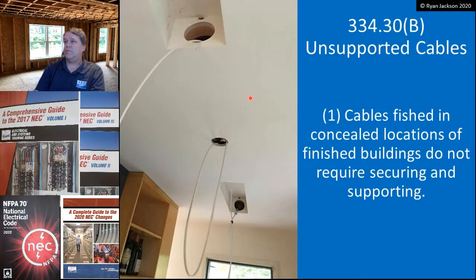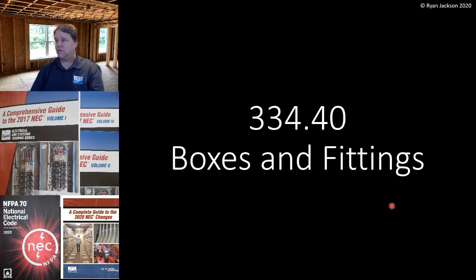All right, one more thing and then I'll check the comments. Unsupported cables. Cables fished in concealed locations of finished buildings do not require securing and supporting. Makes sense. And if Chris is still online, I think he sent me this picture. So this is a finished building. They just used a hole saw to cut holes, and then they'll end up replacing those. Hopefully they didn't hole saw a 5-inch hole right through that floor joist. I never noticed that. That probably sucks. But assuming that's not a floor joist, then we're okay. You don't have to secure and support your wires.